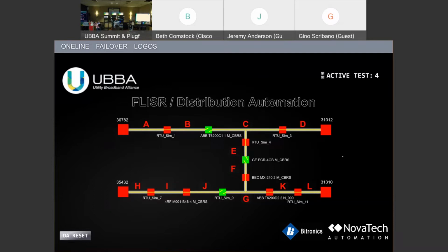Some utilities use different settings. After that, I'm going to reclose the breaker and see if that fault's still there. It's kind of abrupt, so we close the switch, energy starts flowing down the line, and if it is a transient fault, it'll stay closed in and you'll just have your lights blink. If it's not a transient fault and the wire's actually laying on the ground or there's some more significant fault, it will again see the fault current and will open up, but this time it's going to open up quicker and it's going to wait longer, maybe 5 seconds, maybe up to 20 seconds, and then it's going to try one more time. If it tries that one more time and still sees that fault current, it's going to lock out. And that lockout means I'm not going to try to automatically operate anymore.